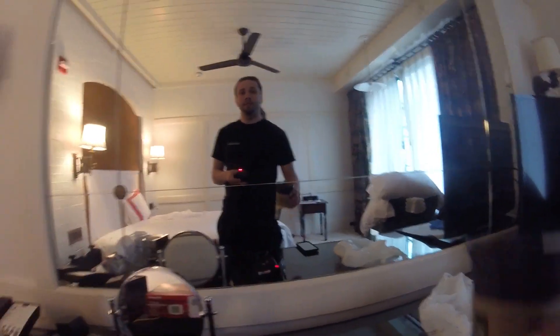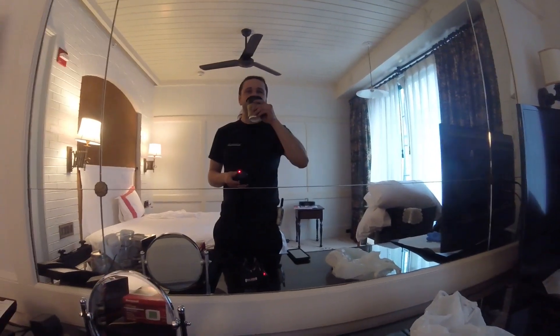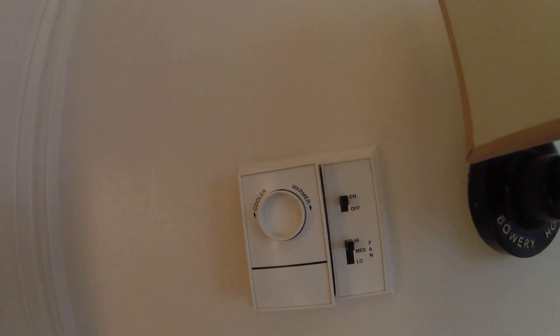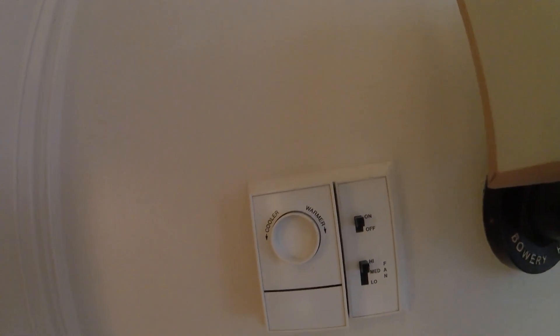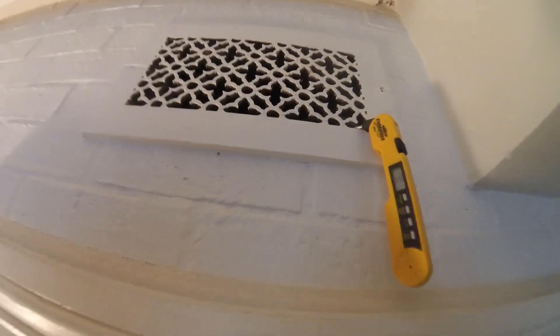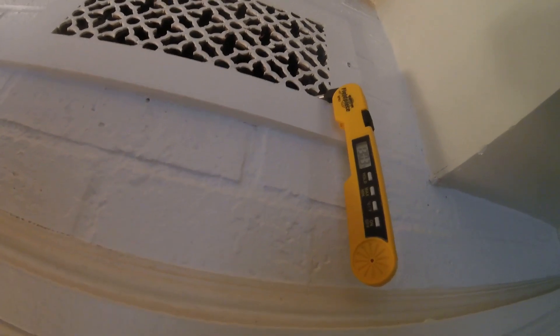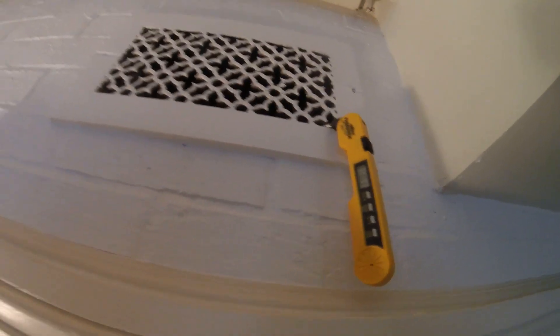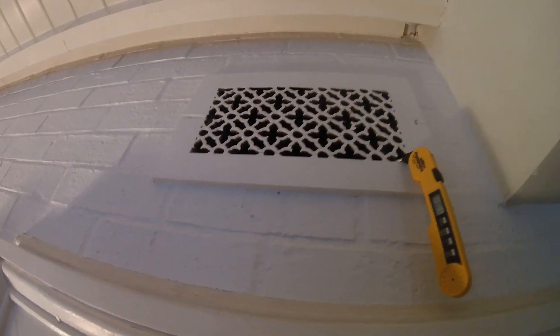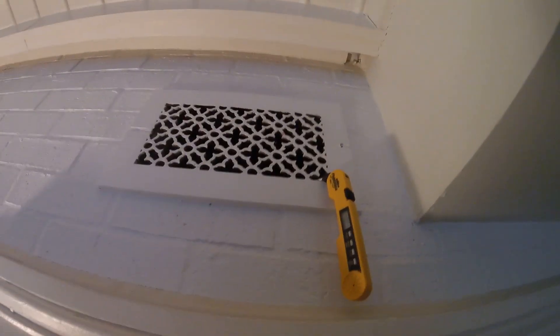Rule of thumb before any service call, give a sip of coffee. The fan is set to high, the thermostat is set to the warmest point. We are blowing warm air, we have 130 degrees. I'm going to turn this thing on and off and let's see if the temperature comes down and make sure that the water valve closes before we start changing thermostats.